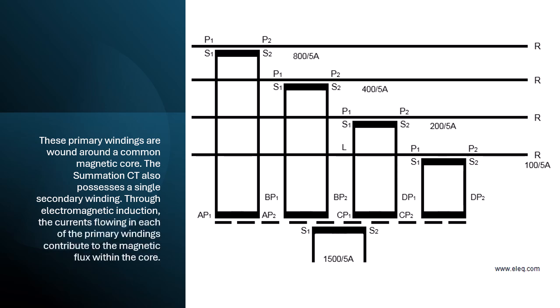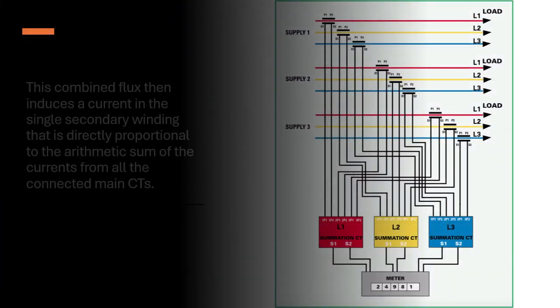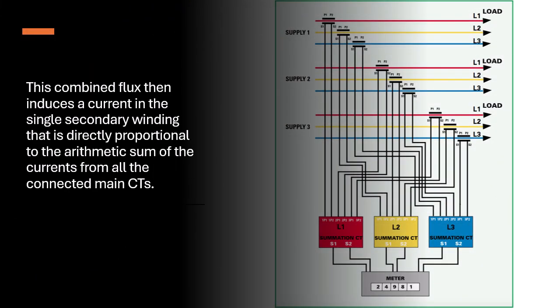The summation CT also possesses a single secondary winding. Through electromagnetic induction, the currents flowing in each of the primary windings contribute to the magnetic flux within the core. This combined flux then induces a current in the single secondary winding that is directly proportional to the arithmetic sum of the currents from all the connected main CTs.